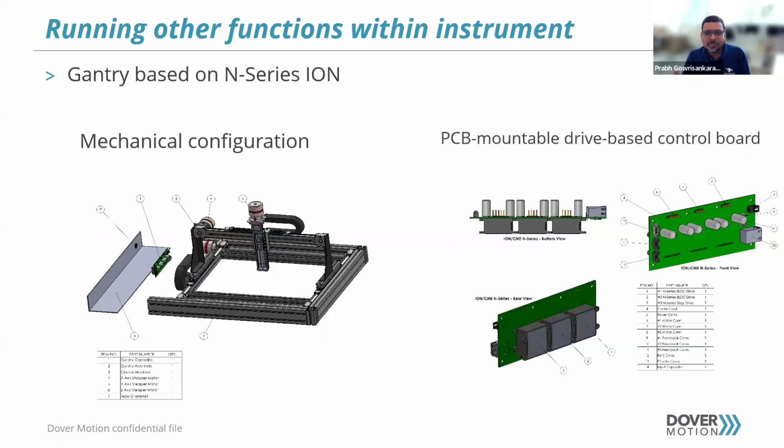Some of the lab automation guys don't want to touch the amplifier side. They don't want to do the analog part of it. So this has an integrated amplifier. And this is showing a gantry example for liquid handling, pipetting, lots of different use cases. And it's showing a three-axis, one drive per axis controlling the XYZ there.